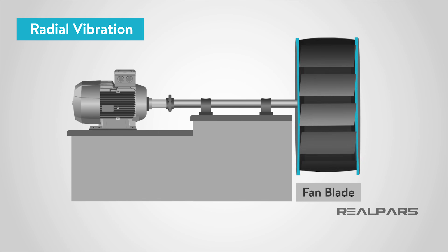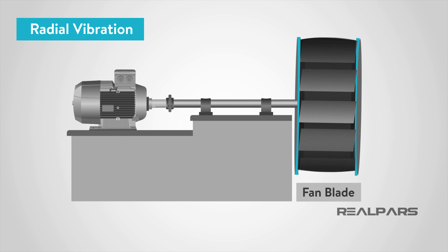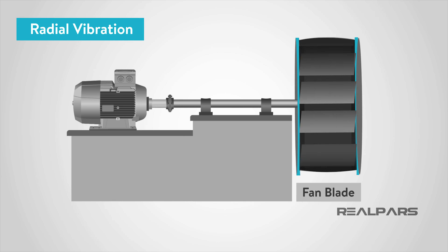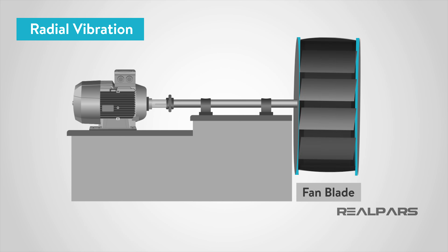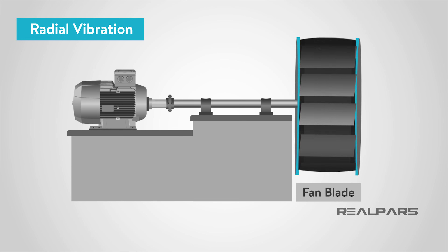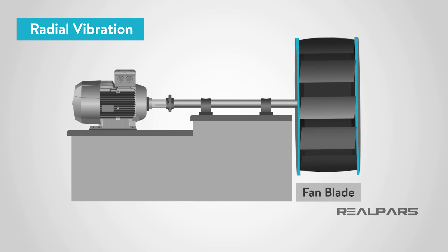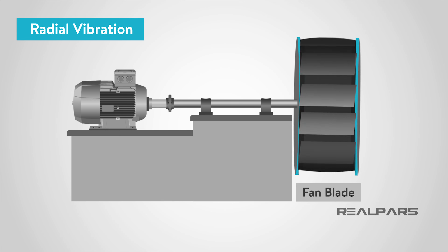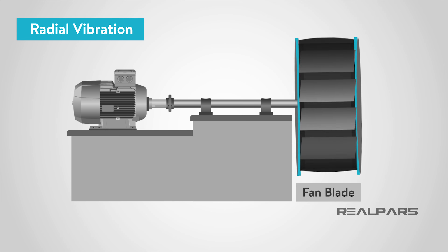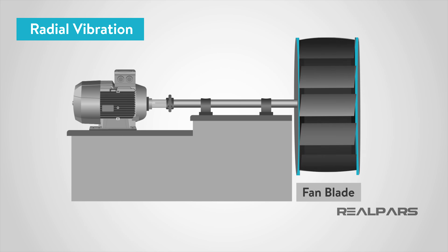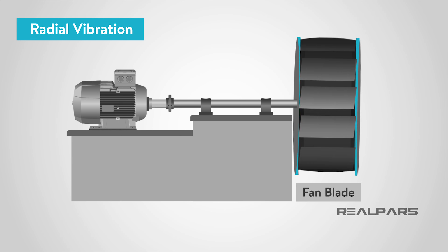Radial vibration occurs as a force applied outward from the shaft. Radial vibration would occur if there is a heavy spot in the motor as it rotates. If there is a deformed fan blade, as the fan spins, the deformed fan blade would pull outwardly on the shaft of the motor causing radial vibration.